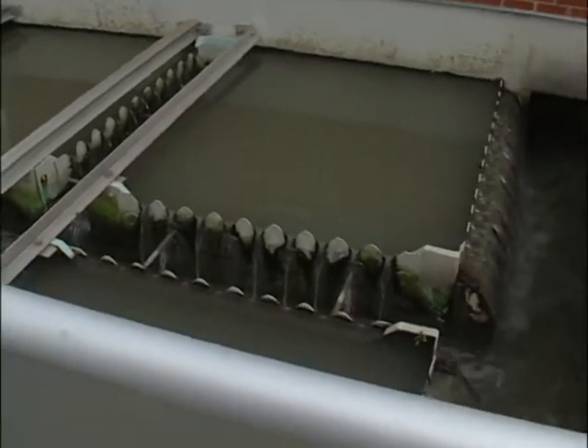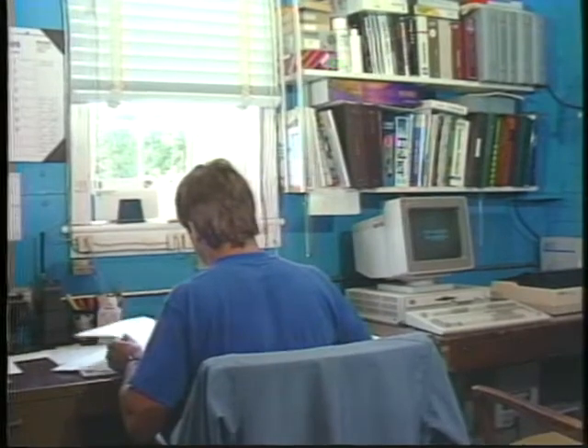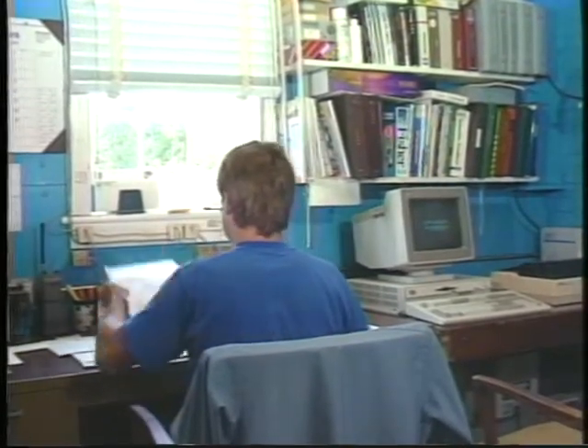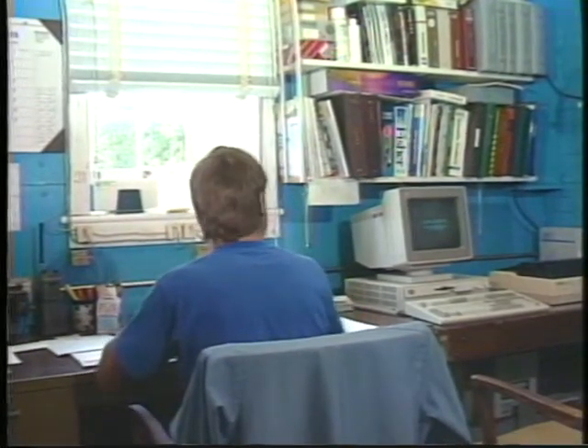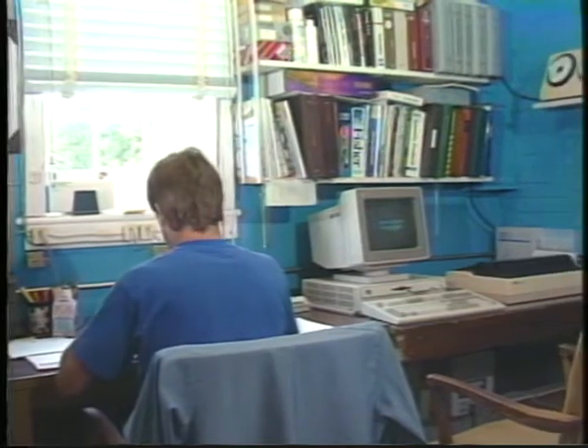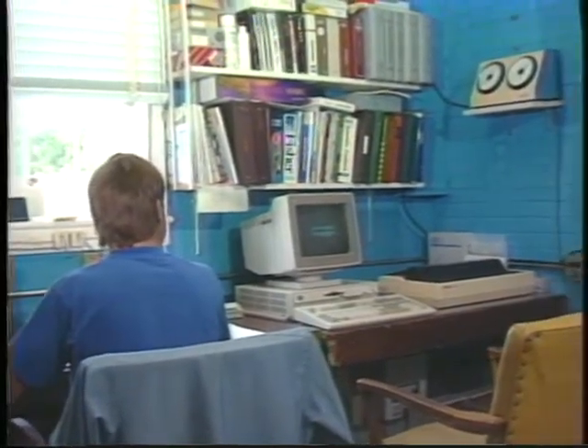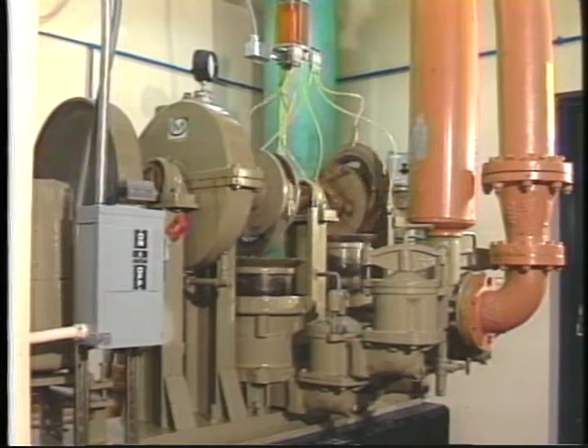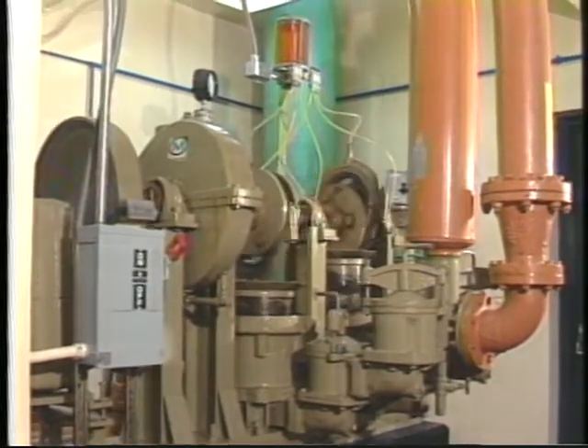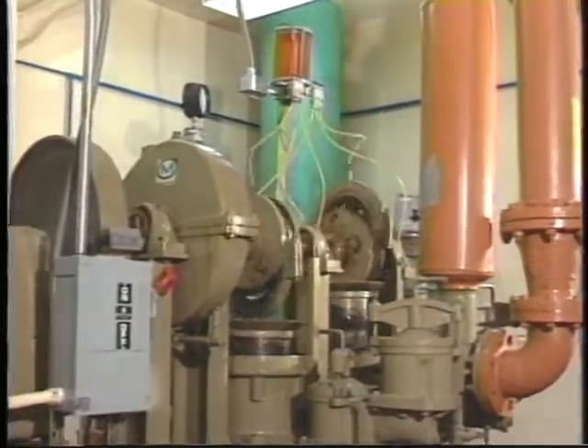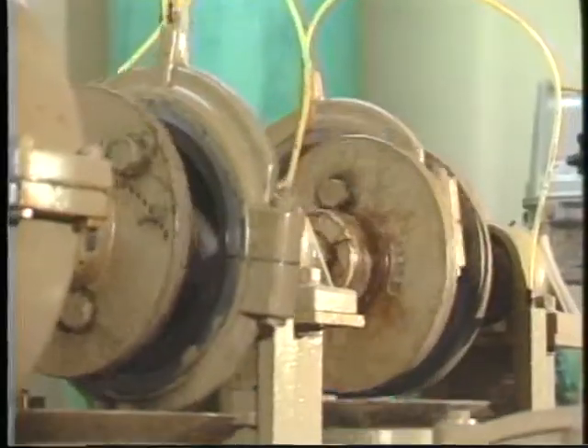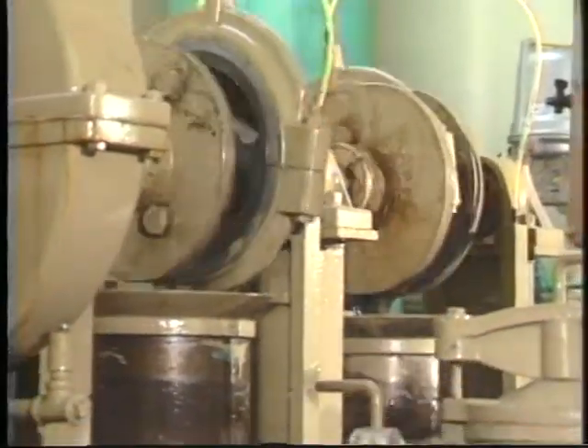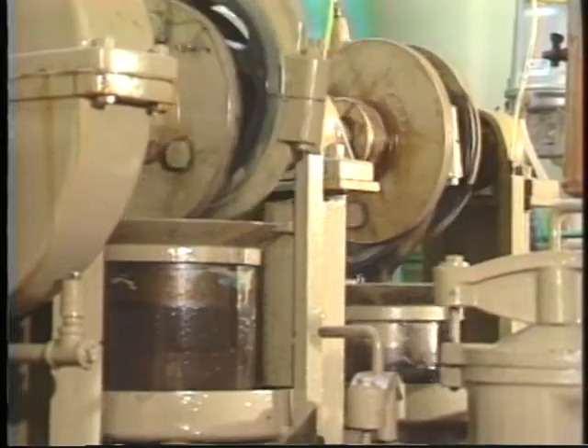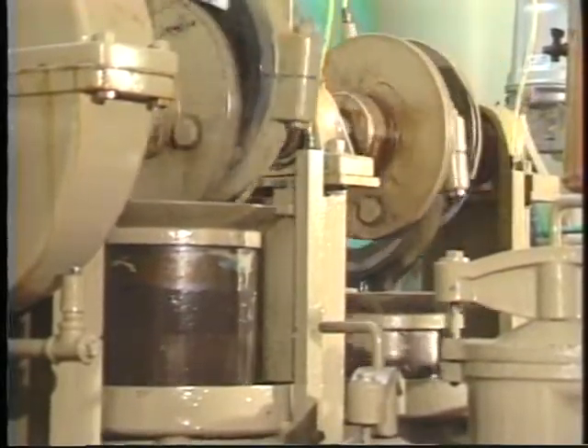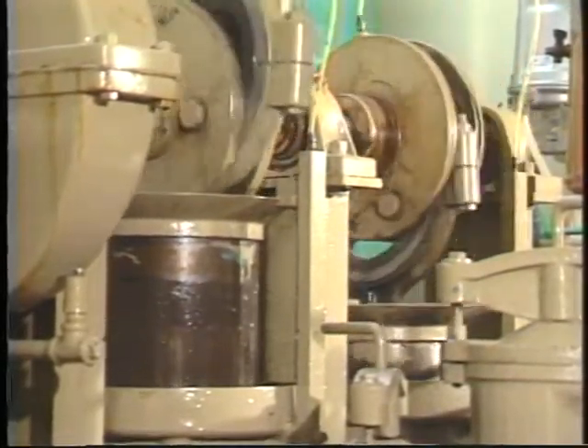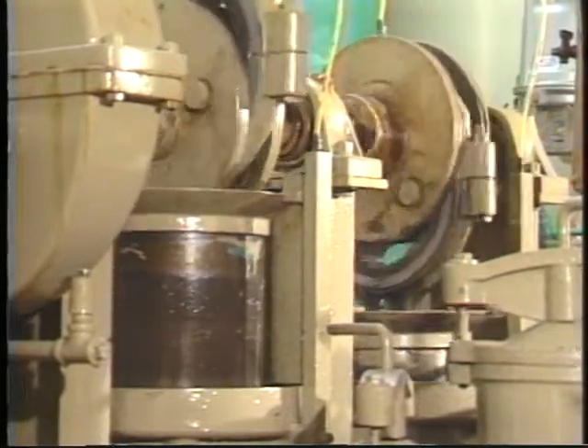clarifier unit. It is essential for the operator to be familiar with the design and loading conditions of the clarifier in order to operate it properly. Timely removal of floatable and settled solids is necessary for proper operation of the clarifier unit. Most commonly, primary sludges are removed from clarifiers with a positive displacement type of pump. The most common type of pump used for this purpose today is the piston pump.